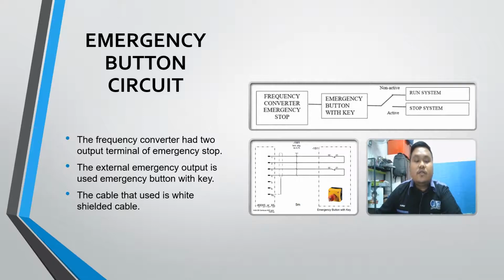In the terminal output of the frequency converter, there are two terminal outputs for the emergency stop button. For the diagram above, one of the terminal outputs for emergency stop of the frequency converter is connected to the emergency button with the key in the control room. A white shielded cable is used for the emergency connection to ensure safety for students and equipment. The emergency button is used to stop the testing in an emergency case. For example, if the system cannot be stopped when the laptop is hanged, the key can switch to shut down all the system in the testing cage.